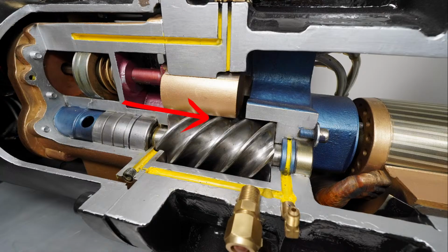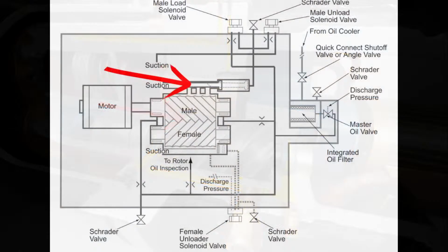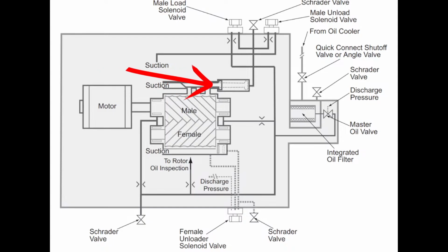compressor. This is a Hanbell, so in case that's throwing you off, this is not the same Trane compressor, but the same theory applies. This slide is going to move towards the discharge side of the screw rotors in that process. So looking at this picture, this slide is in a fully loaded position, where the little ghosting here would show a fully unloaded position. So if you ever open one of these up, these are really easy compressors to service in the field, and servicing this slide is something we would do.